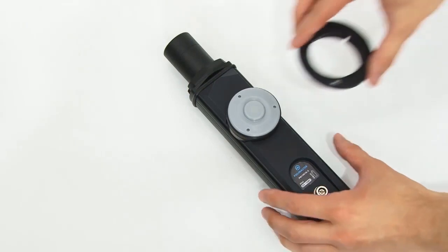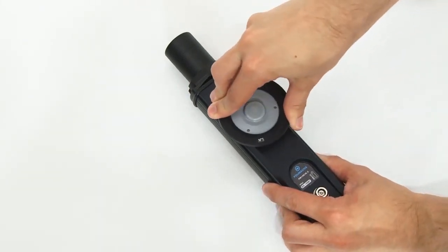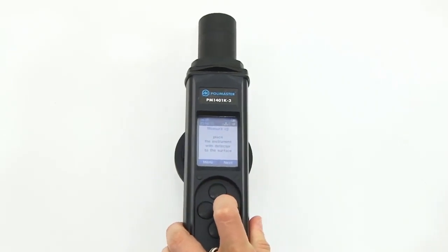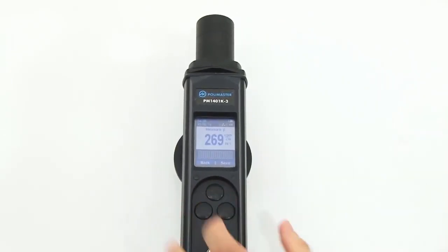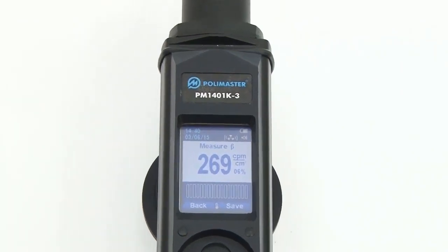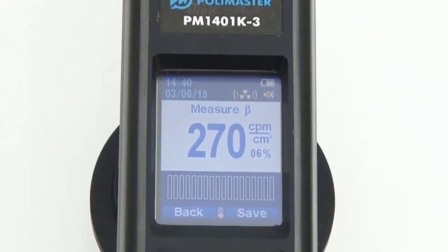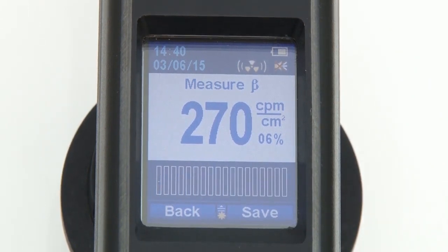Then remove the spacing rings and install the gamma-beta filter. Spacing ring number 3 is installed on the gamma-beta filter. Place the instrument on the inspected surface and press the Next button. Now the instrument displays the value of beta radiation flux density, which you can record when the statistical relative error satisfies your needs.